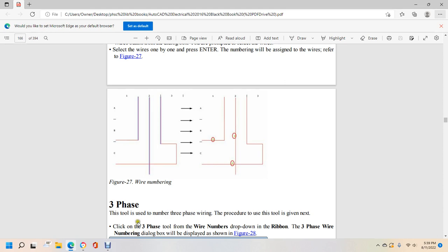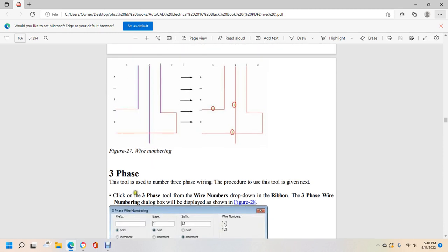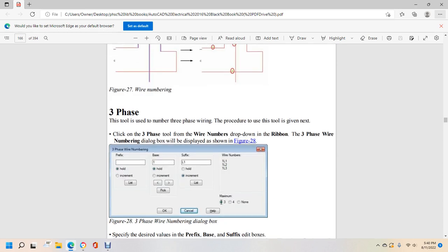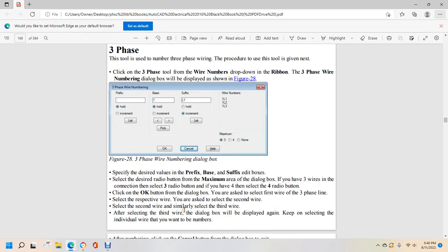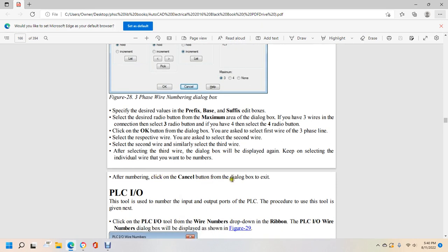Three-phase wire numbering. Click the three-phase tool from the wire number drop-down ribbon. The three-phase wire numbering dialog box will display as shown in figure 28, with fields for prefix, base 1, and suffix, each with hold or increment options, and wire numbers 1L1, 1L2, and 1L3. Specify the desired values in the prefix, base, and suffix edit boxes. Select the maximum radio button — three or four — depending on the number of wires. Click OK, then select the first, second, and third wires of the three-phase line one by one. After selecting the third wire, the dialog box will display again. Keep selecting wires to be numbered, then click cancel to exit.